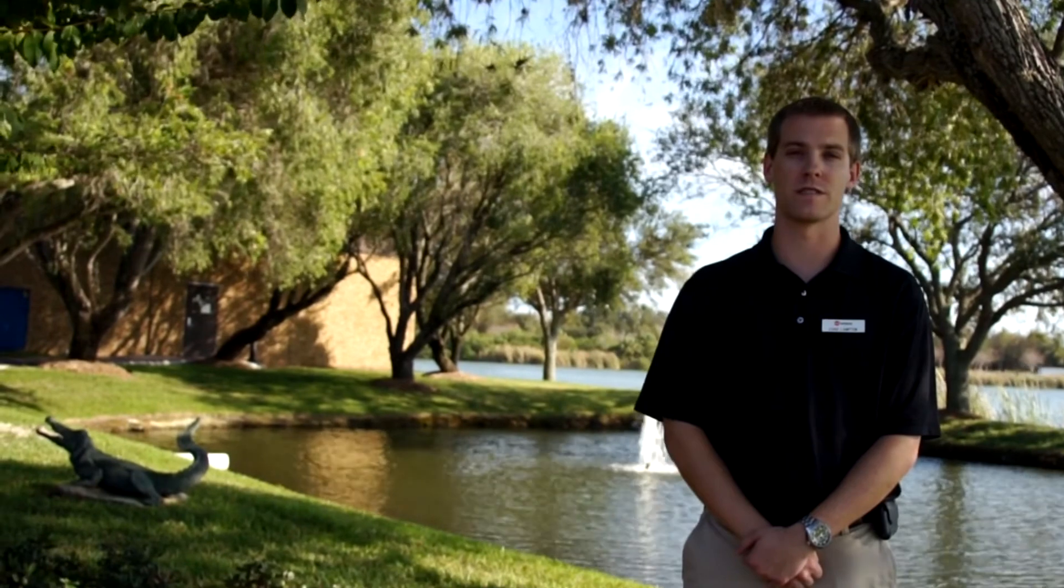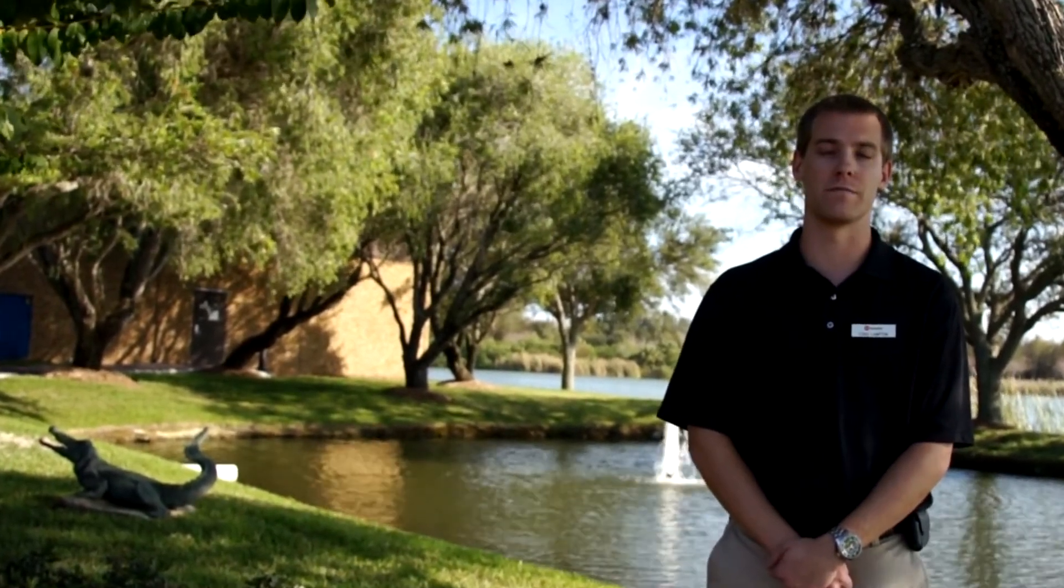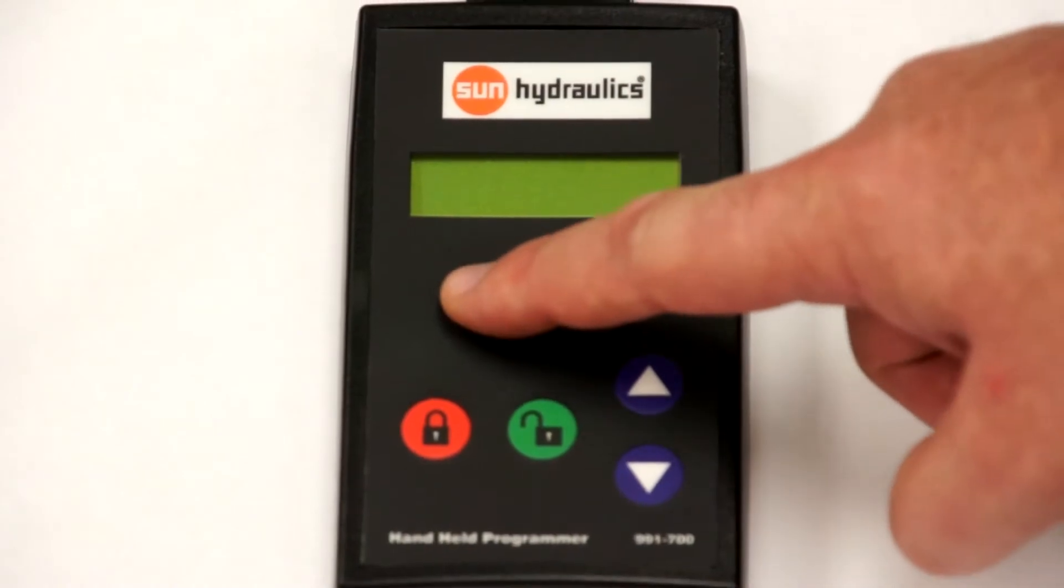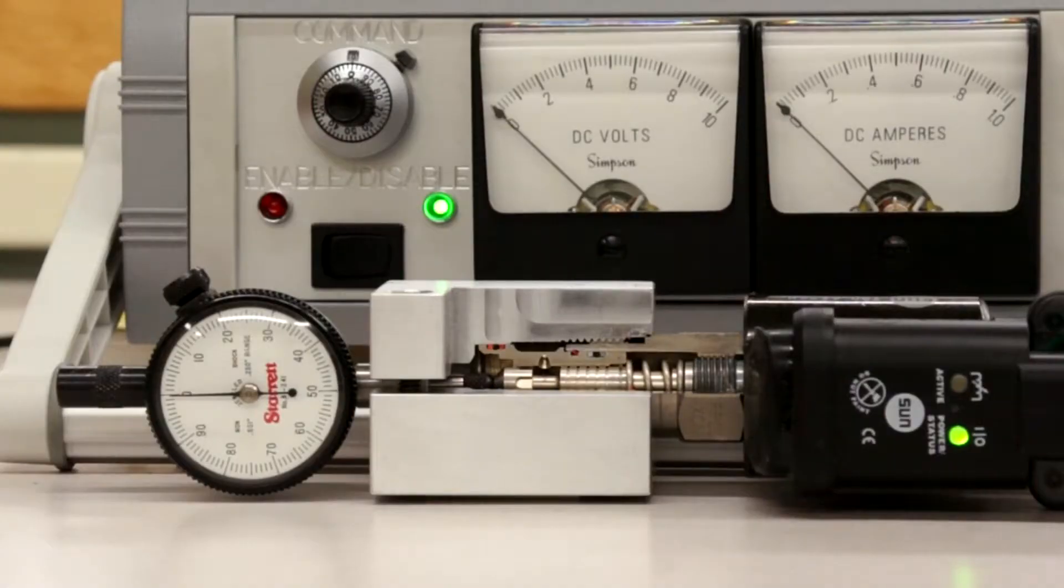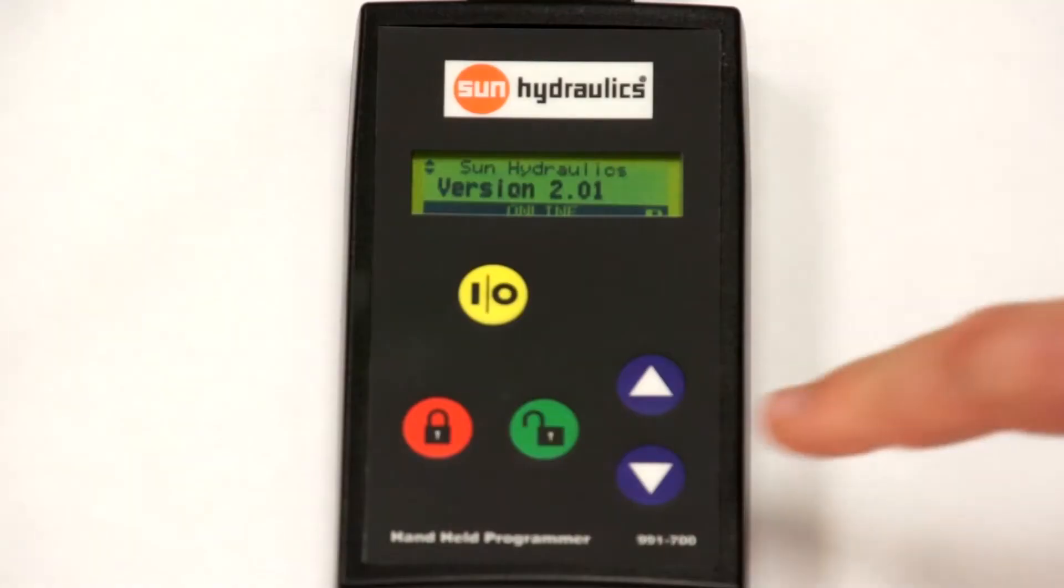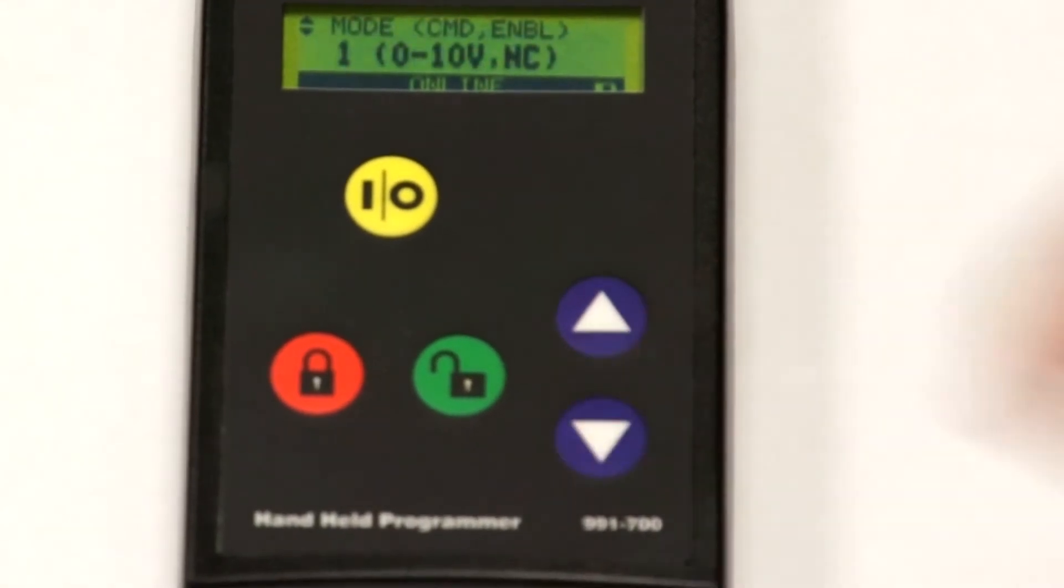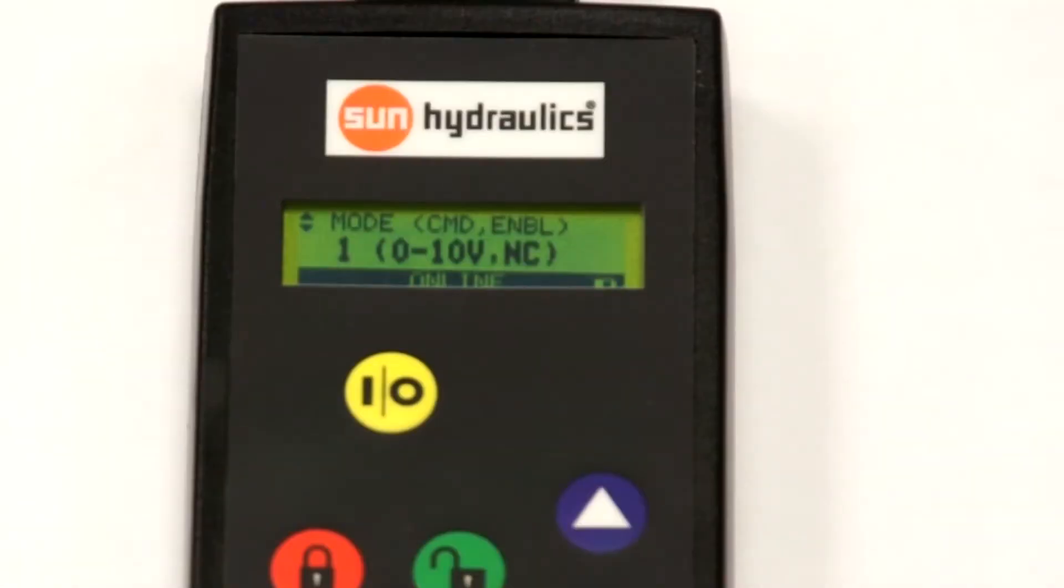Hello, my name is Chad Lampson, I work in the cartridge engineering group here at Sun Hydraulics. Today I'll be going over the 6 modes of operation of Sun's embedded amplifier. Turn on the handheld programmer with the embedded amplifier powered on. Scroll down using the down arrow until you see the parameter called mode of operation.